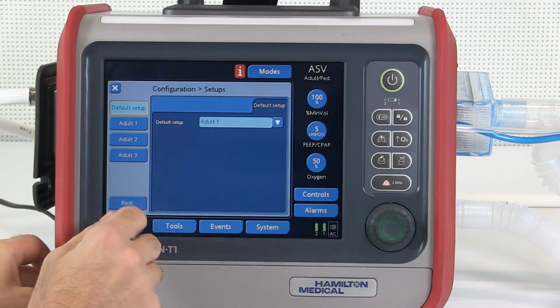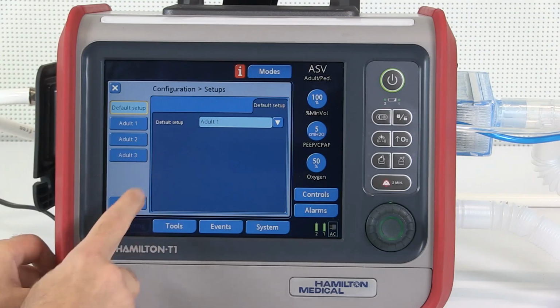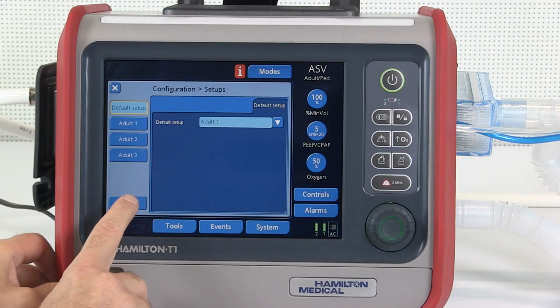In standby mode, configure the ventilator unit with the parameters you will save as a quick setup. Select the patient group, then the gender and height for adult and pediatric patients, or the weight for neonates, the ventilation mode, the mode control settings, and the alarm limits. Also see the operator's manual for more details.